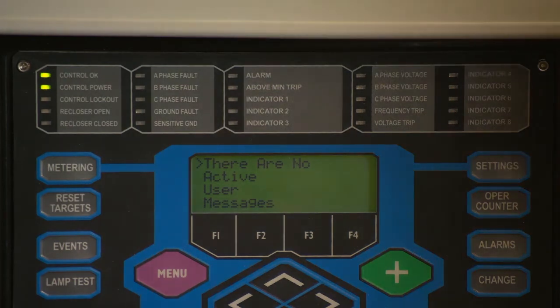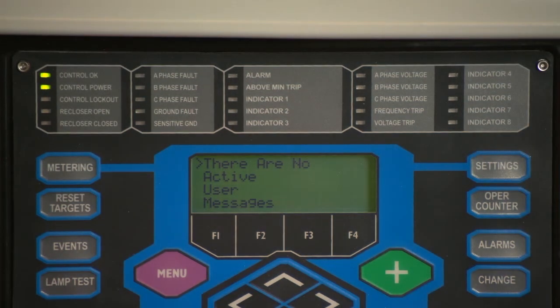Metering. The control provides instantaneous and/or demand metering with programmable integration intervals for the following functions: real and reactive power for each phase and total, including directional, on an individual phase basis. Demand currents on a per-phase basis. Instantaneous currents, including ground current. Instantaneous voltage on a per-phase basis. Instantaneous frequency. Positive, negative, and zero sequence voltages. Instantaneous power factor on a per-phase basis. Metering settings to include demand interval and alarm thresholds for current, single-phase kilowatt, three-phase kilowatt, single-phase kVAR, and three-phase kVAR.